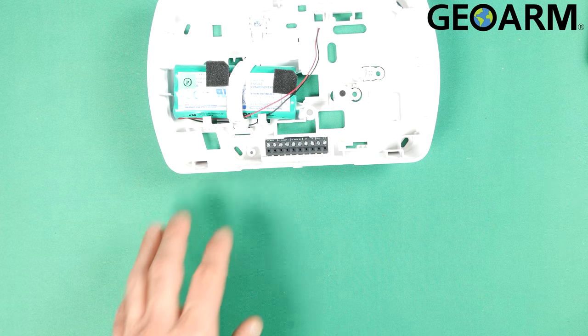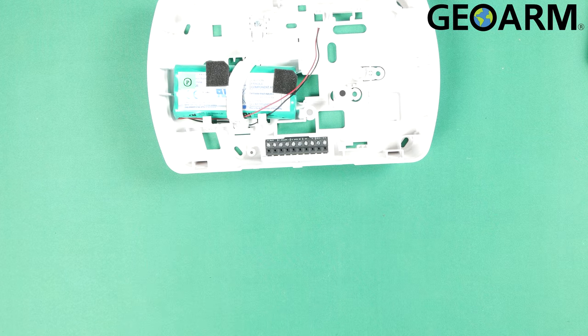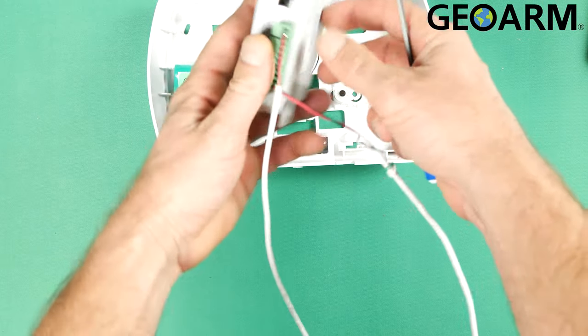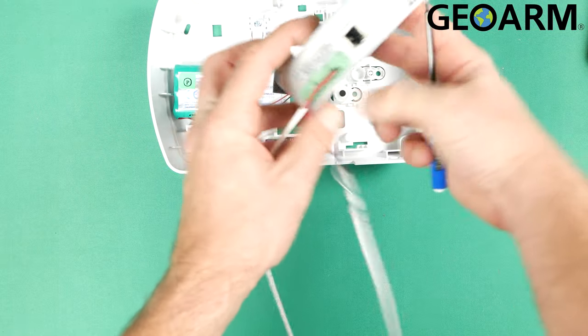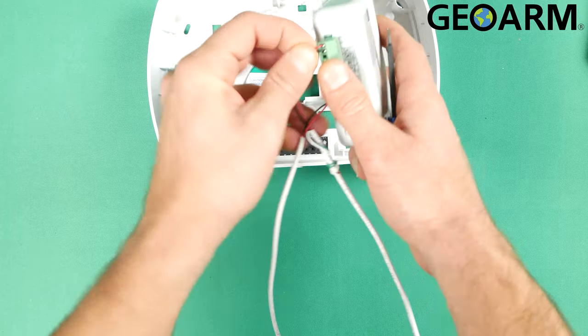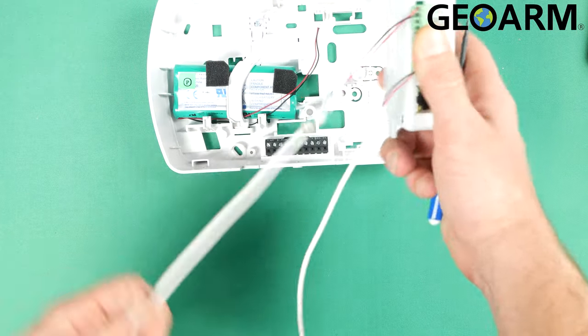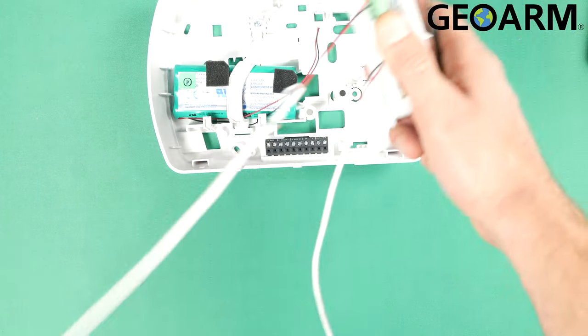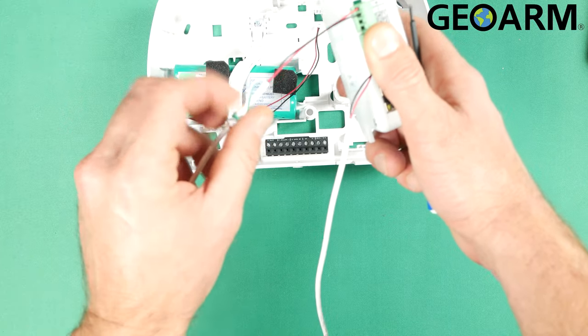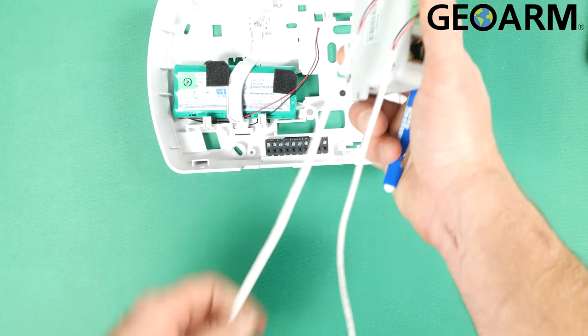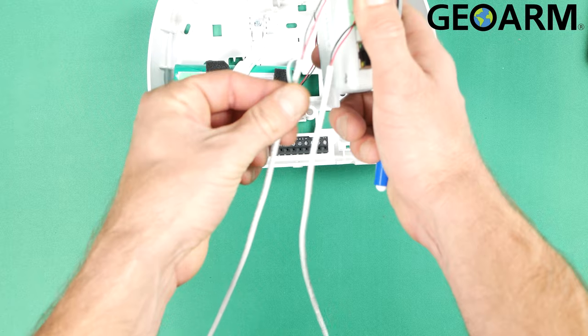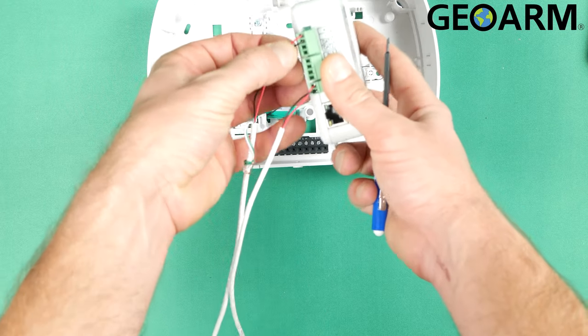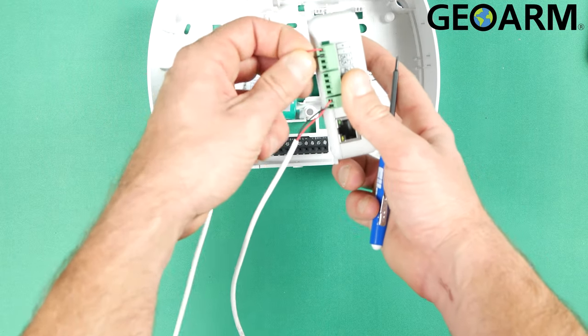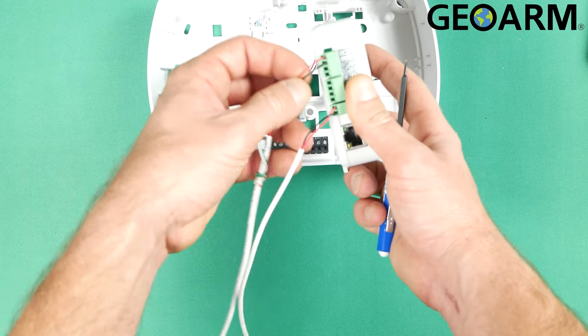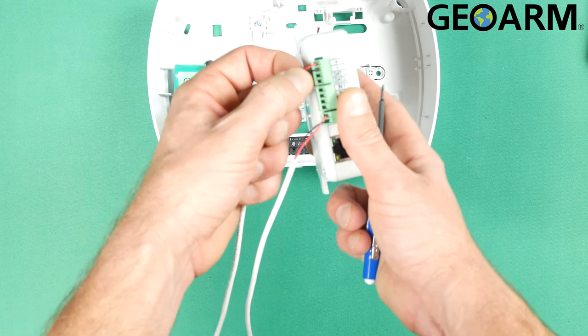So what we're gonna do is grab our communicator after the panel's been opened and powered down. And as you guys can see, I've pre-wired this communicator, so it's gonna be four connections total. So we have two strips of 22 gauge, two conductor. In this case, it's four conductor, but I didn't cut these back because I actually am going to use this again. So you guys can ignore these connections here. Only these matter. So the red wire is going to go to plus or positive, and the black wire is going to go to minus or negative.